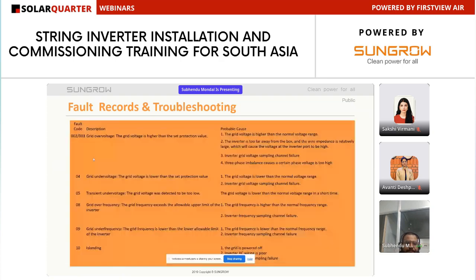So here is the fault record and troubleshooting process. From 2 to 10 are mostly grid related issues: grid over voltage, grid under voltage, transient under voltage, grid over frequency, grid under frequency, and islanding. For grid over voltage, if the grid voltage is higher than the normal voltage range of the inverter, it will show grid over voltage. Grid under voltage, if the voltage is less than the range, it will show grid under voltage. If the grid voltage is lower than the normal range for a short time, it will show grid transient under voltage. Grid over frequency is the same: if it is higher than the range, it will show grid over frequency, and if it is lower than the range, it will show under frequency.